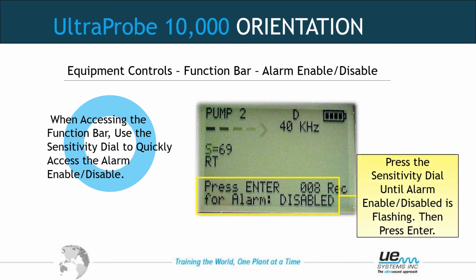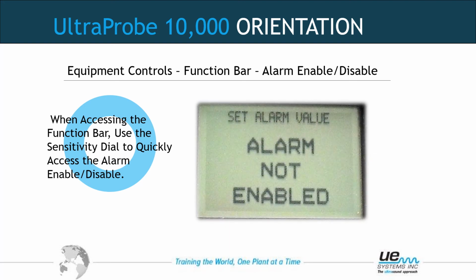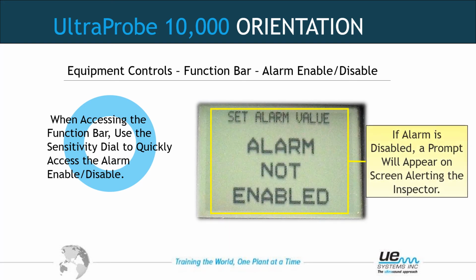Back to the main display. So if you entered into here, your sensitivity was probably flashing. So 2 clicks again, sensitivity to frequency to function bar. Rotate it till you see press enter for alarm. It's either disabled or enabled. If you were to press that sensitivity right now, you would see alarm not enabled. If the alarm had been enabled, it would say alarm and what the value of that first alarm test point was.